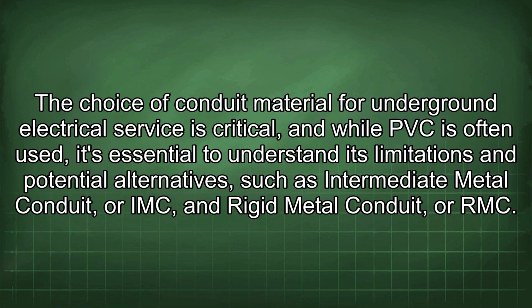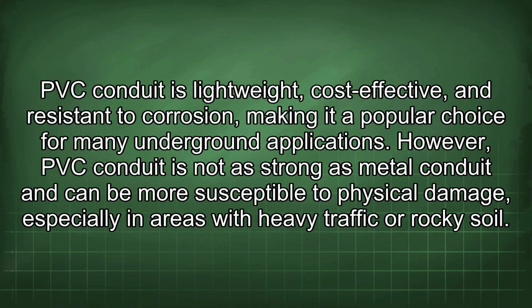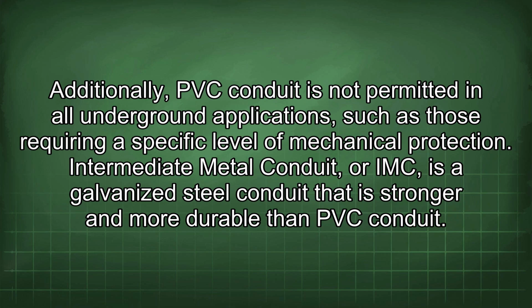The choice of conduit material for underground electrical service is critical, and while PVC is often used, it's essential to understand its limitations and potential alternatives, such as intermediate metal conduit, or IMC, and rigid metal conduit, or RMC. PVC conduit is lightweight, cost-effective, and resistant to corrosion, making it a popular choice for many underground applications. However, PVC conduit is not as strong as metal conduit and can be more susceptible to physical damage, especially in areas with heavy traffic or rocky soil. Additionally, PVC conduit is not permitted in all underground applications, such as those requiring a specific level of mechanical protection.